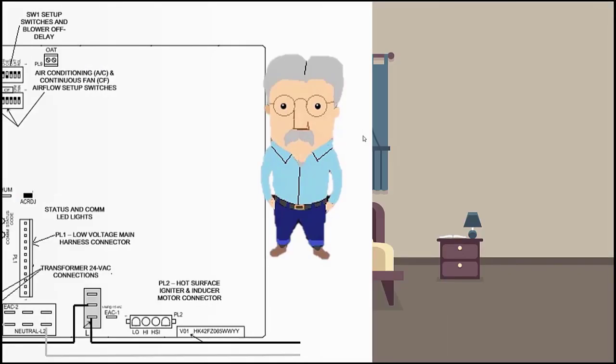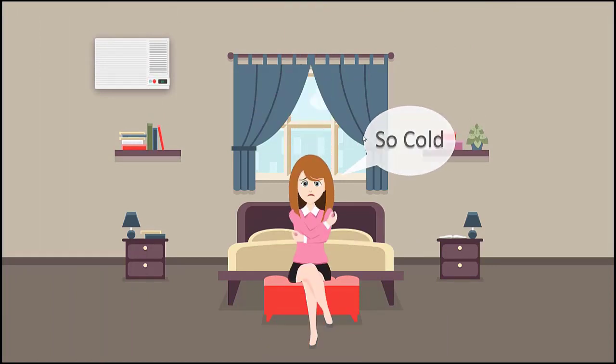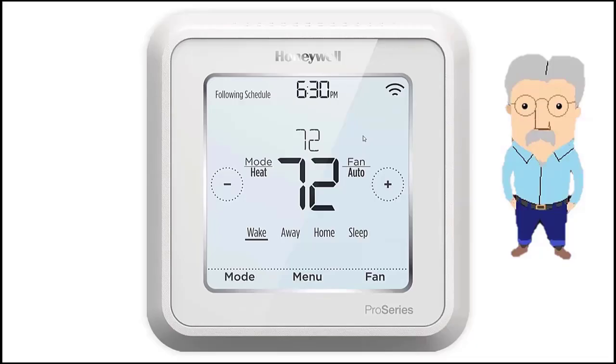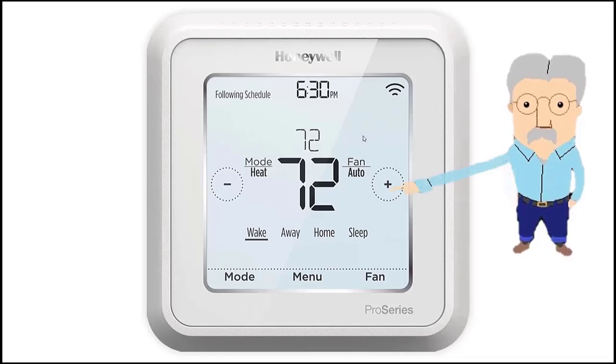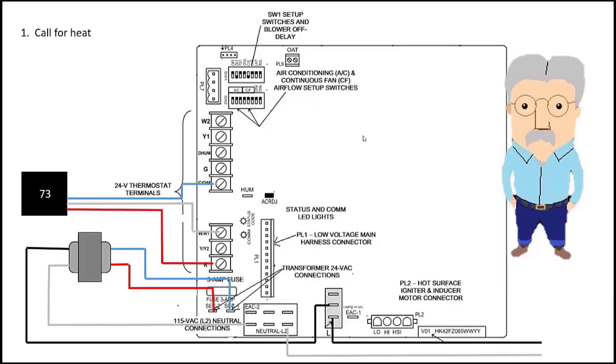The first in our sequence is a call for heat. What can we do to help this young lady? So let's walk over here to our thermostat and adjust the heat up. There we go. We got it up to 73 degrees. And let's go back to our board now. So we have a call for heat. Let's run a wire from thermostat to W1. When W1 is called, that is a call for heat. And that starts the entire sequence.